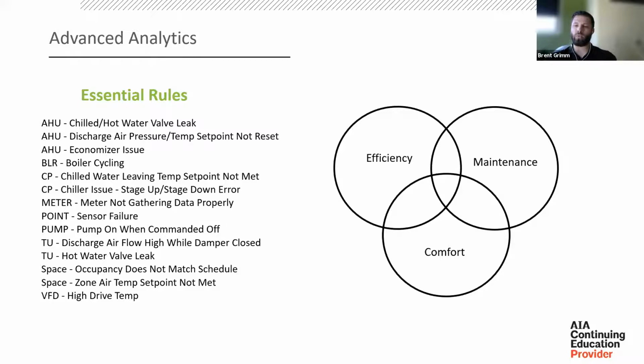What this rule will do is look at the mixed air temperature and the supply air temperature of that air handler and compare that DT to the chill water valve position. Now, if the program is seeing the air temperature drop from the mixed air sensor to the supply air sensor, and the chill water valve feedback is showing a 0%, then that's going to trigger an alarm, letting the user know that there's an issue and this valve appears to be leaking.